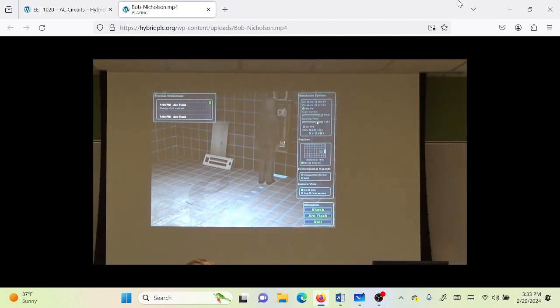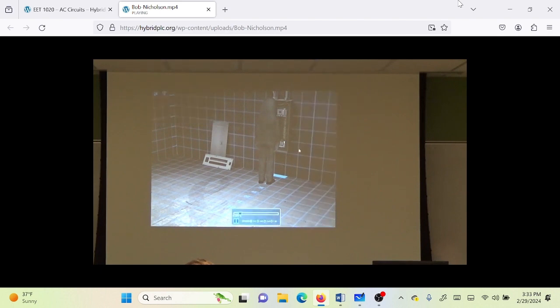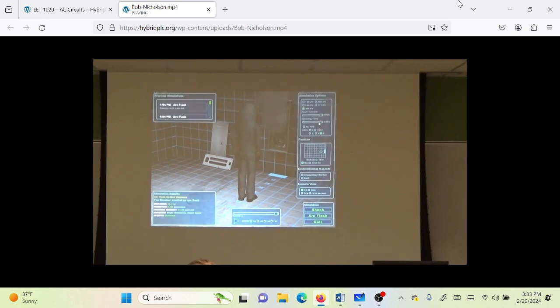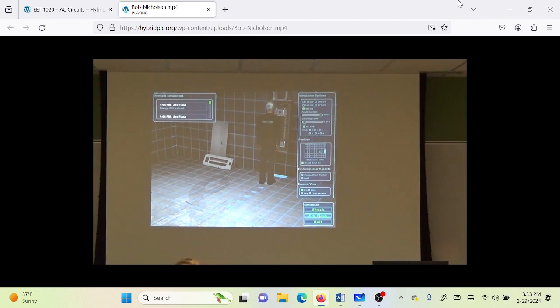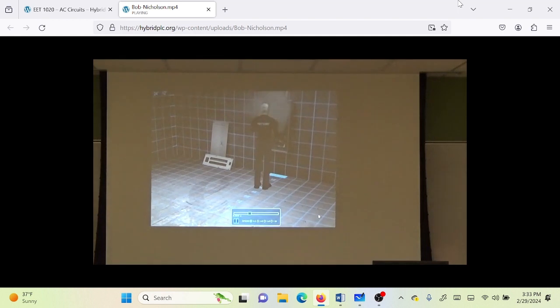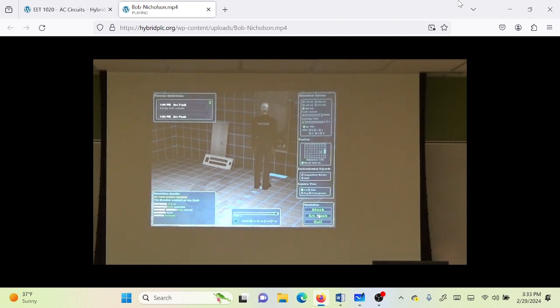I'm going to take it all the way up to 60,000 amps for 2 seconds. The clothing will take up to 40 calories of energy, which you'll see in a minute, and then the clothing is going to fail too. There is no permanent solution to the clothing. Now I'm going to take this guy, move him back just a little bit, and I'm going to have no PPE on him. 60,000 amps. Anybody want to tell me what's going to happen to this guy with no PPE? Disintegrated, right? Here we go. Nothing. Why? Huh? I turned the time down.